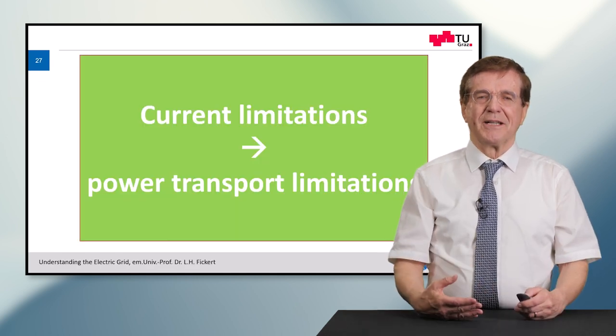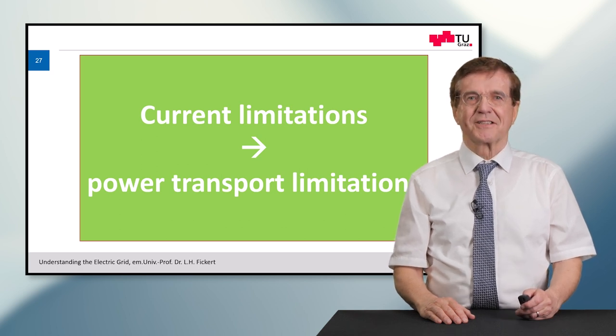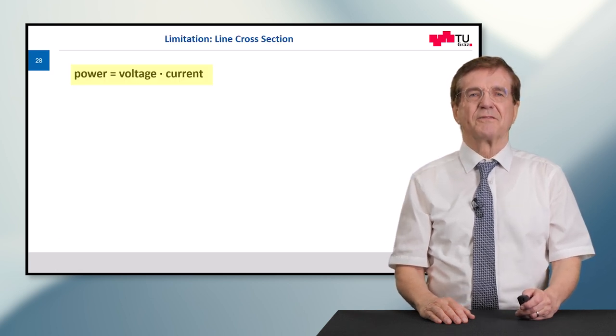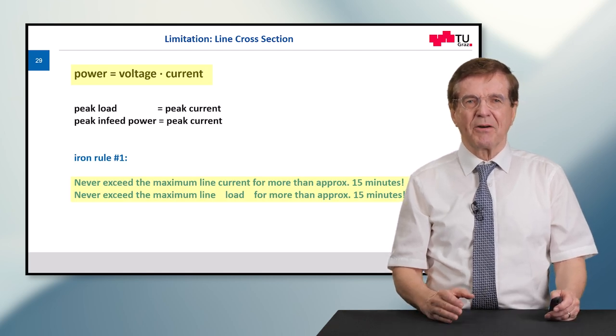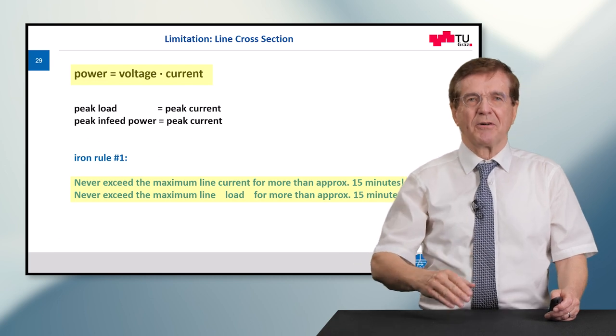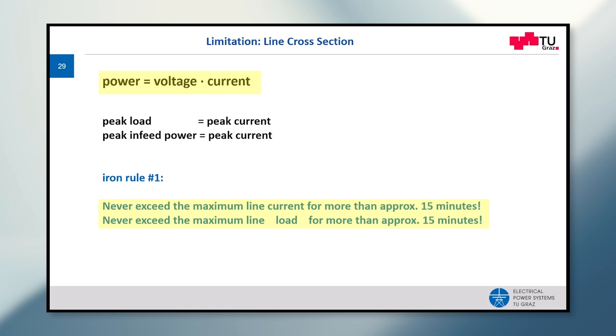Now from these contemplations, the current limitations which lead to power transport limitations can be derived. So power is voltage times current. This means the peak load means peak power, and this means peak current. And the peak infeed power for generation as well means again peak current. And here we come to iron rule number one. This means never exceed the maximum line current for more than 15 minutes. Never exceed the maximum line load for more than 15 minutes.